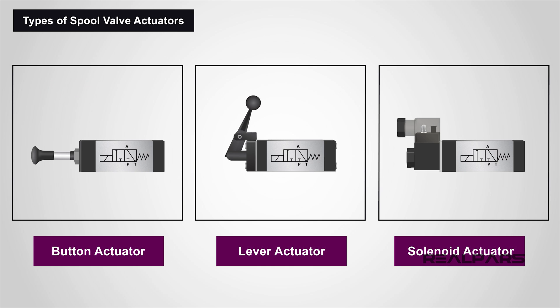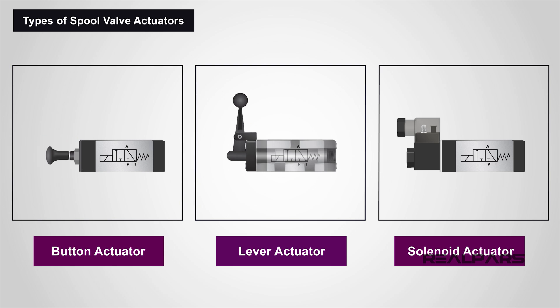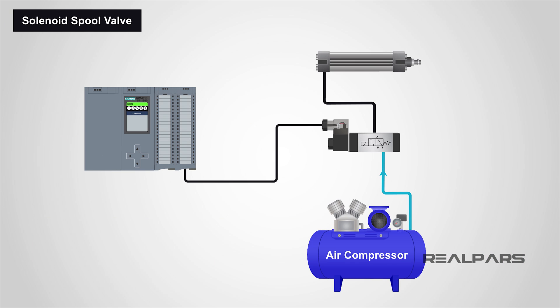The spool can be moved in many different ways: manually using a button or a lever, or as part of a larger control system using a solenoid actuator. Whatever the method chosen to control the valve, all that we are doing is simply pushing the spool to move within the housing, and by doing this we are allowing or blocking the path between the ports.